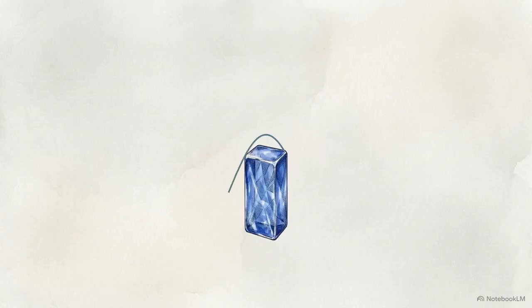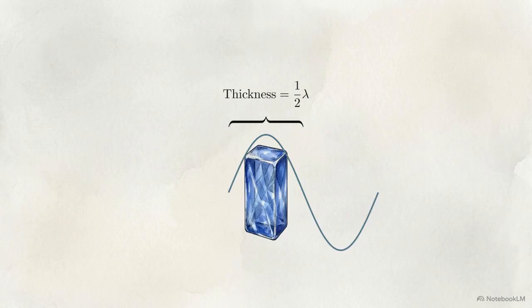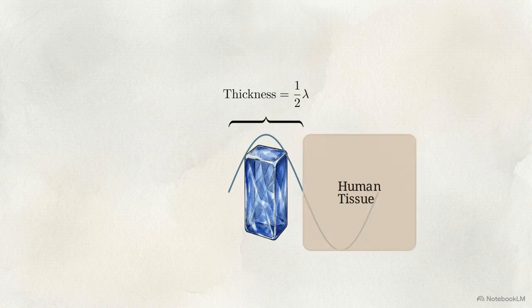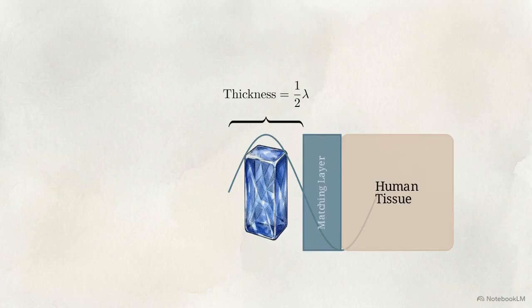To resonate correctly, the crystal must be manufactured to a thickness of exactly 1/2 of the operational acoustic wavelength. But the high density of this crystal creates an acoustic impedance mismatch when placed against softer human tissue. Without intervention, the majority of the sound energy would reflect off the skin and be lost. To solve this, a matching layer is permanently bonded to the front of the crystal array, acting as a step-down bridge for the impedance difference. To function, this matching layer must be machined to a thickness of exactly 1/4 of the acoustic wavelength.